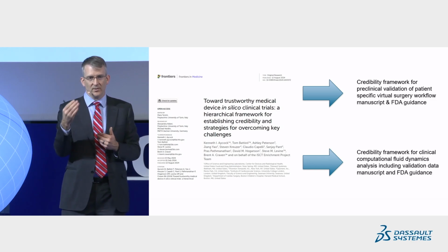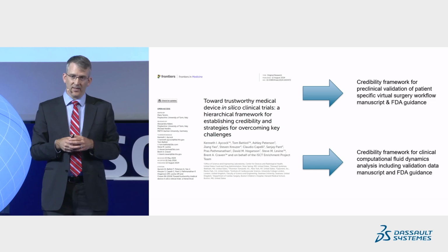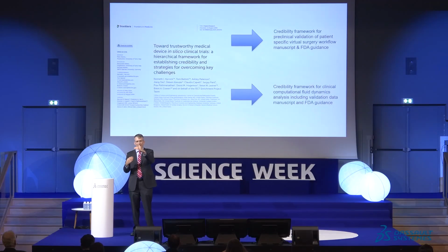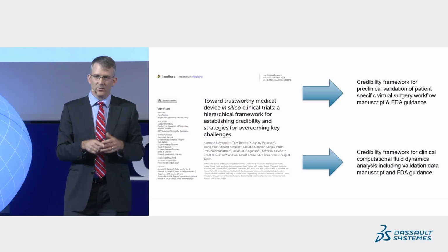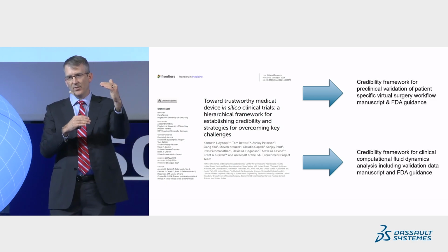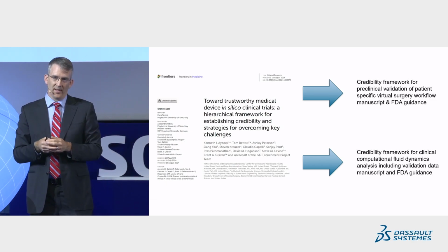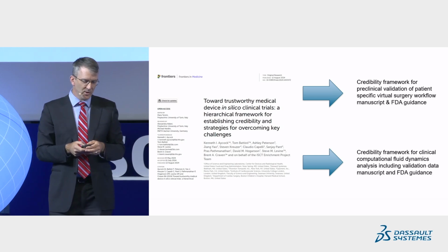So we're in the process of finalizing a manuscript in collaboration with the FDA that's going to outline both our preclinical validation work and how the credibility assessment that's used in modeling and simulation for devices is now tailored to this preclinical assessment. Similarly, for our patients with computational fluid dynamics, we're taking that same approach and taking the credibility assessment that the FDA has outlined and then adapting that for how you apply computational fluid dynamics in a clinical setting, and about to publish that also.